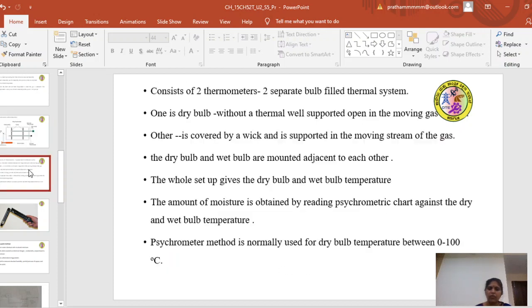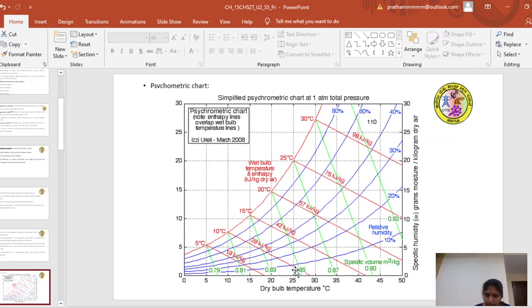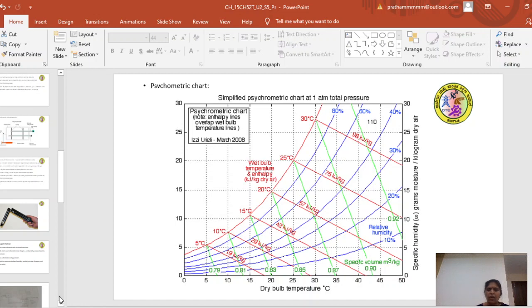When you select a dry bulb temperature, for example 25 degrees, the vertical line is shown. If the wet bulb temperature is, say, 24 degrees, the slanting line is shown. Where those two lines meet, the corresponding horizontal line gives the specific humidity. This is how to measure the humidity using the psychrometer.